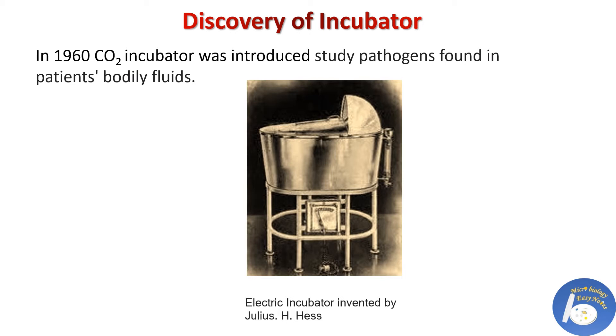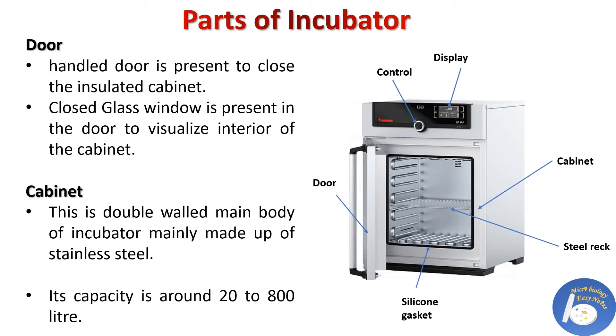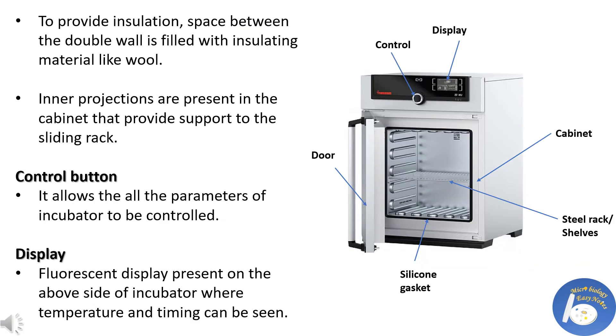Earlier lab incubators were very simple. Julius H. Hess, an American physician, was the first one who introduced the electric incubator. Today's incubators are advancements of this electric incubator. The first part of the incubator is the door, which is present outside the cabinet and helps to close the insulated cabinet. A closed glass window is also present in the door to visualize the interior of the cabinet. Next is the cabinet — this is the double-walled main body of the incubator, mainly made up of stainless steel, with a capacity of around 20 to 800 litres.